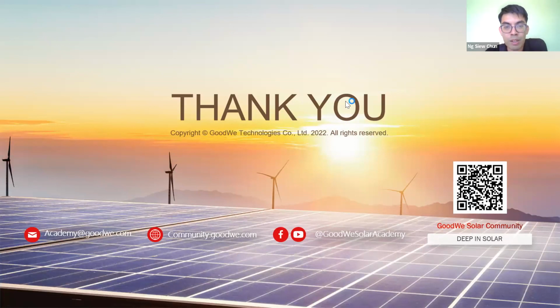Okay, we have one question from Mr. Sidek. Can I use it for totally off-grid solutions? The answer would be yes. Like I said, we have an off-grid mode, but you need to be very careful with it, because basically you only have our inverter to support that. You need to be very careful during your design to make sure that your loads will not cause any overcurrent from the inverter, or else the inverter will keep on tripping. So this is the off-grid mode. If there are any questions regarding the designs, we can always discuss them further offline.